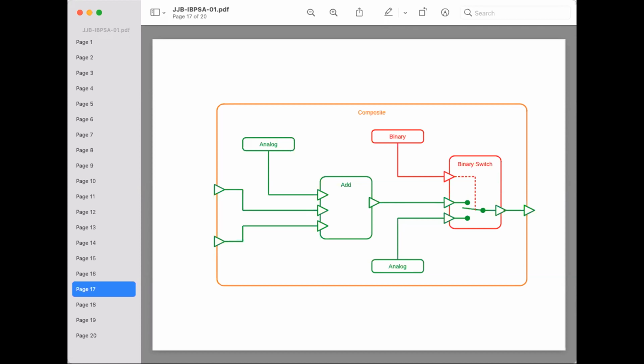One of the important efforts of the Open Building Consortium that's leading this piece is that the sequences of operations that are in Guideline 36 have been modeled in Modelica in some cases, so they have been in some sense proven that the sequence will operate as expected when it's implemented in the real world. So now the effort is, how do we take these sequences of operations out of Guideline 36, build models of the schematics of the systems, line up those properties, and line up those values with the simulations.